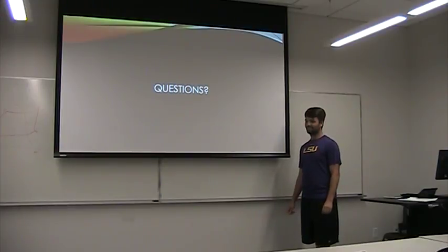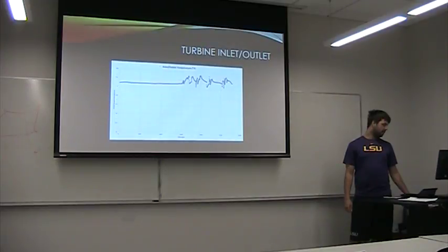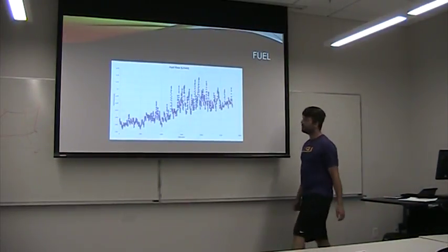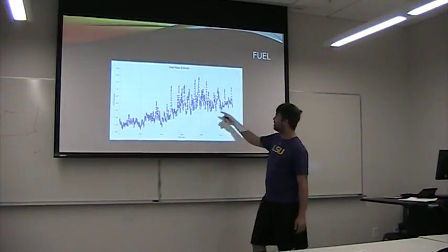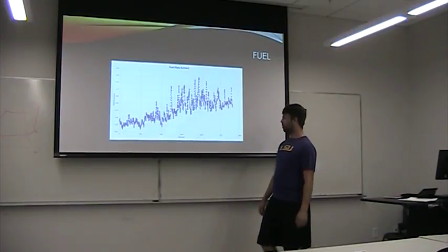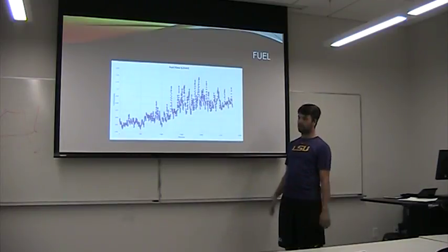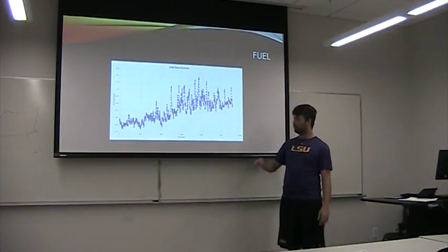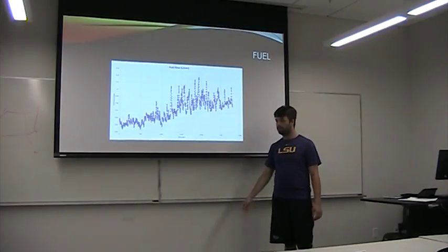How much fuel did you say you used again? What were the values between? The values were between 5.65 and 5.72, which is the absolute highest, in liters per minute. So it stayed pretty consistent, and I used that mass flow rate of the fuel when calculating the heat added in by the boiler to determine the efficiency.